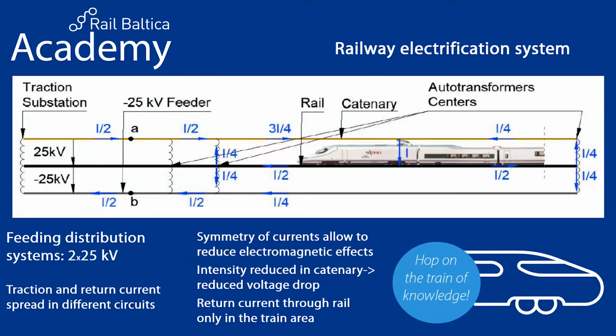We also have some current going in the negative feeder. If we look at this return traction current, only half of the intensity used to power the train comes back through the rails, compared to the previous solution where the full intensity was coming back. But closer to the substation, in the area where there are no trains between the auto transformer and substation, all the intensity is going through the feeders and not as return traction current.